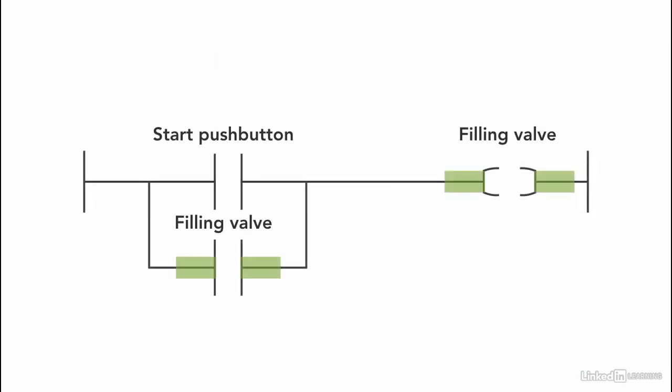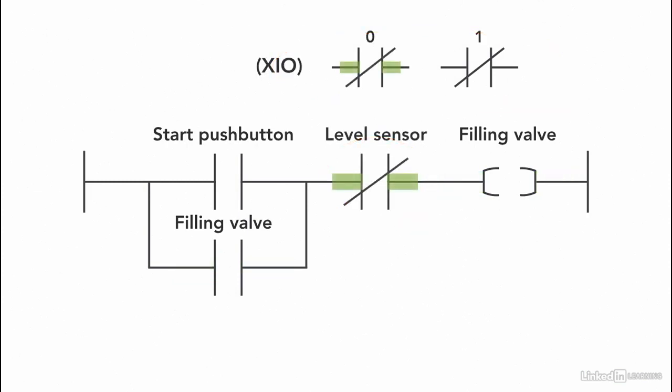So I'm going to use the instruction here. I need to choose an instruction that is highlighted when the memory location is 0 to keep the continuity. So we are going to use an XIO instruction for the level sensor. Remember that the instruction is highlighted and activated, but the physical sensor is not on. The level sensor has not reached the required level yet.